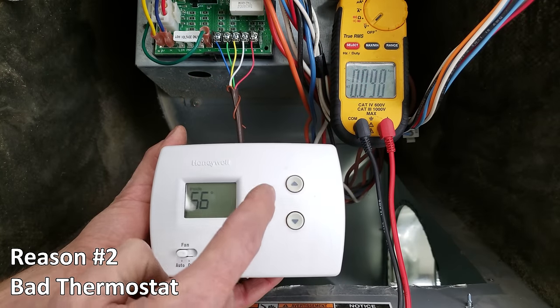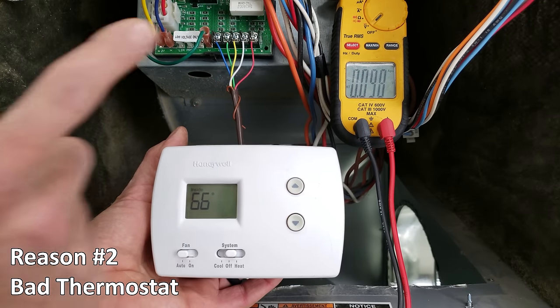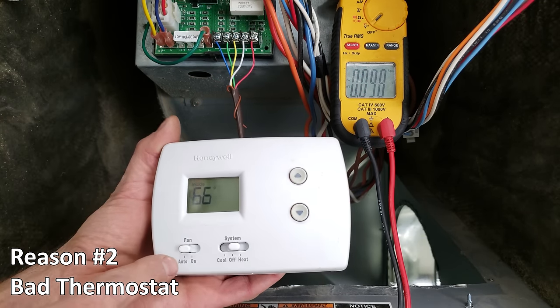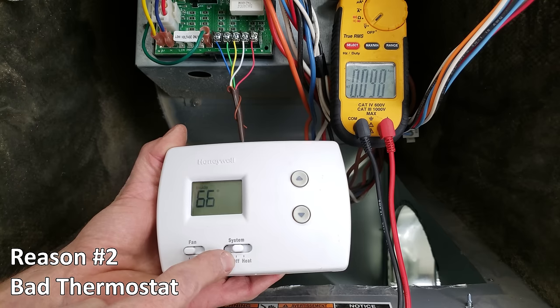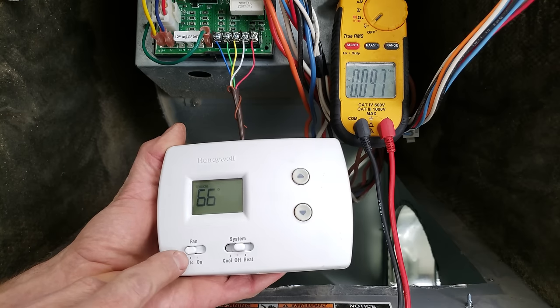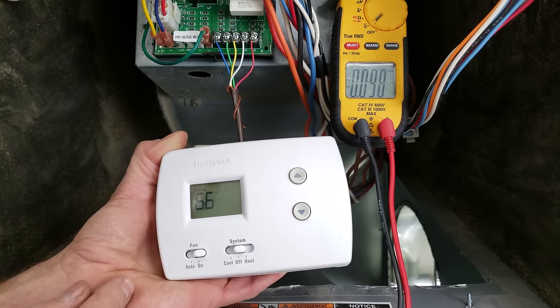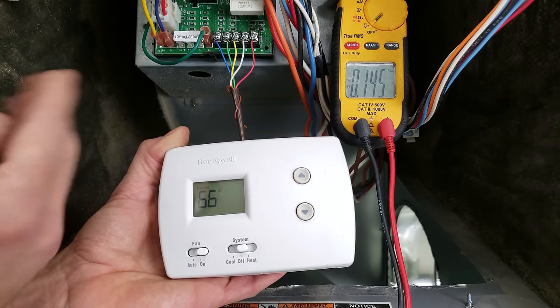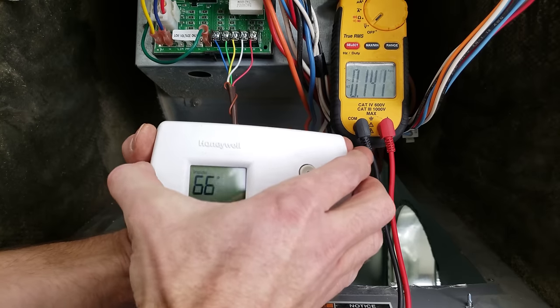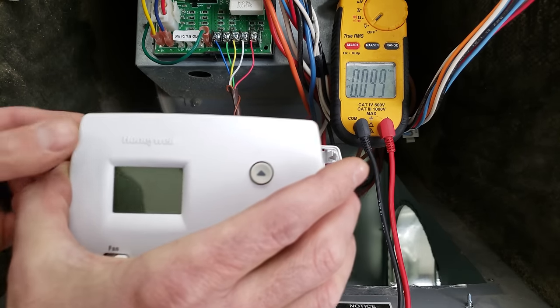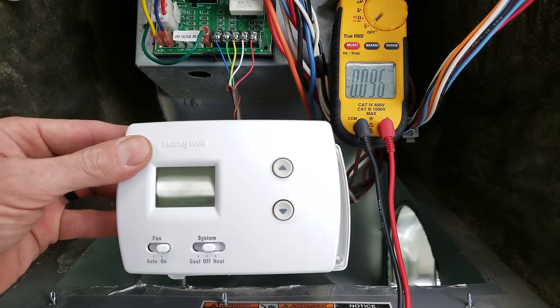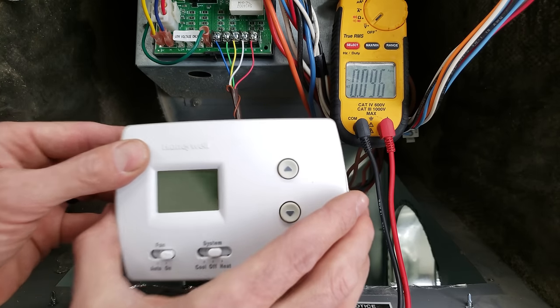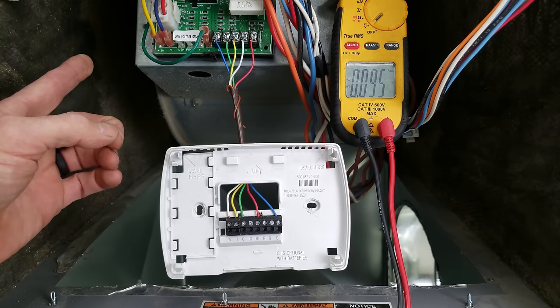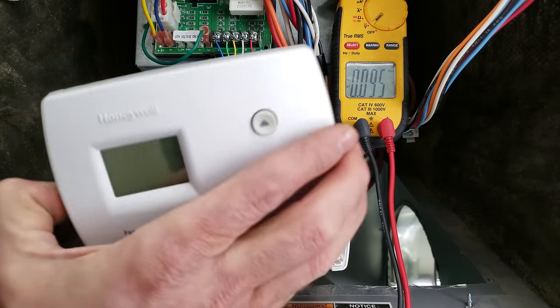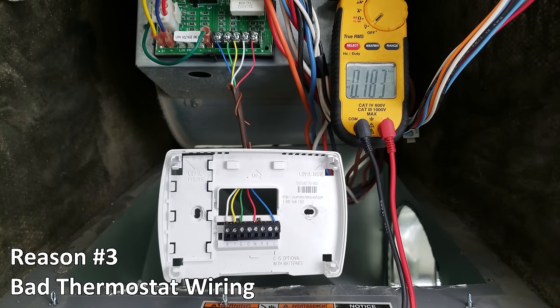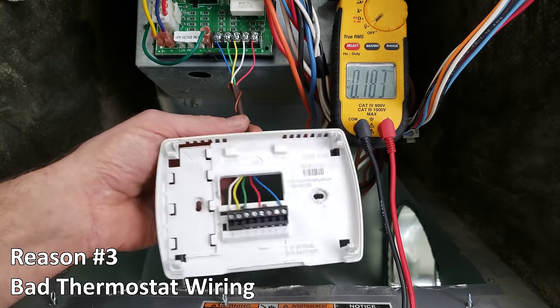Problem number two is when you have a thermostat that's accidentally telling the blower motor to turn on, even when you have it set on auto and off. So just say that this switch was not on and the blower motor was running. What you could do is just remove the thermostat face itself. And if you remove it and then the blower motor shuts off, then you know that the thermostat face is the problem.